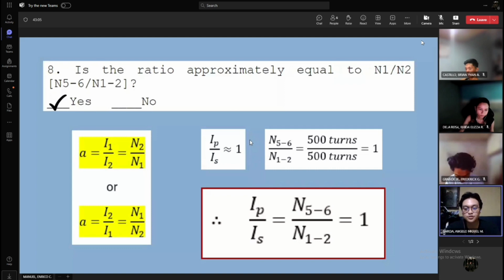Okay, so from the previous question, we have our ratio of the primary current to the secondary current, which is approximately equal to 1. If we notice, it is not exactly equal to 1. It is just an approximation. We also notice that the current in the secondary is slightly lower, maybe just a matter of decimals. And this is because of the copper losses experienced within the windings of the transformer. So our current ratio is still approximately equal to 1.